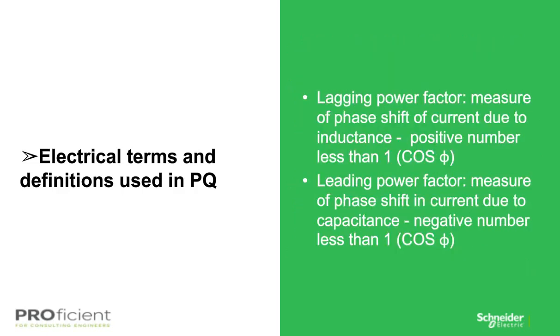So further breaking down some of the phase-shifted power, I want to start with two different types. The first is lagging power factor, which is the measure of current phase shift, typically caused by inductors, where the current lags behind the voltage and is shown as a positive number between 0 and 1. And the second is leading power factor, the measure of current phase shift, typically caused by capacitors, where the current leads in front of the voltage and is shown as a negative number between 0 and -1.